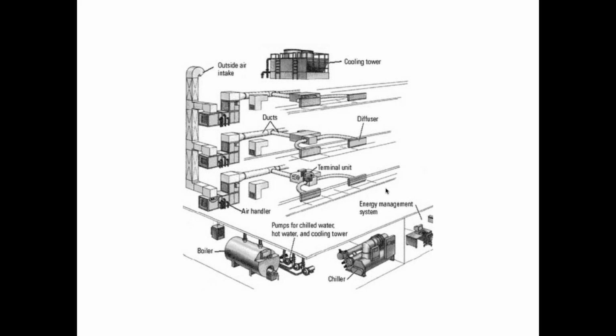Each one of those little groups shares a thermostat. So for instance, if there was a thermostat in this room and we had a terminal unit supplying this room, we could adjust the temperature to whatever we wanted, and we would only get the amount of cold air or hot air that we needed to keep this room perfect. We wouldn't have to worry about whether the guy next door is cold or hot, right? So that's called a variable air volume system.